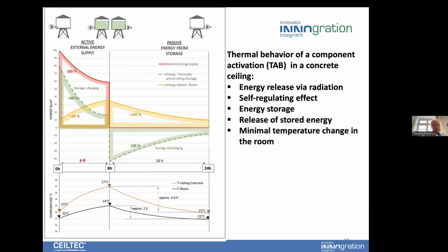You can see here, if within 8 hours we put in energy, we raise up the temperature, and we measured the energy going into the concrete and the energy going out of the concrete. We put in 100% during this time, and only 35% of this energy is being released immediately into the room, while the other 65% is being stored in the slab, and it can be used during the next 16 hours to heat the room as it should be done normally. After this time, after the 16 hours, we reach the temperature again, what we had before.